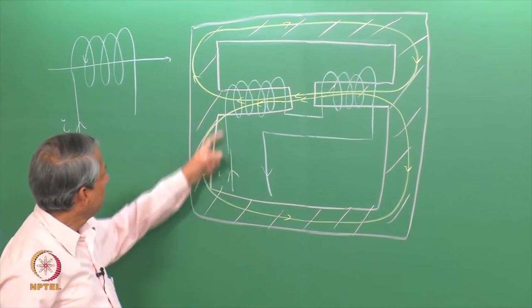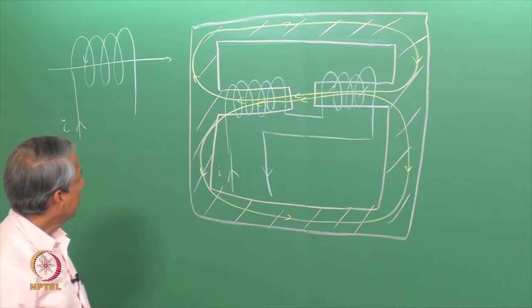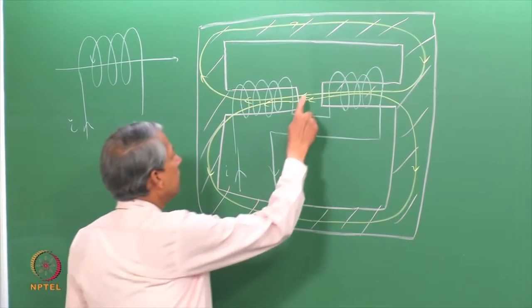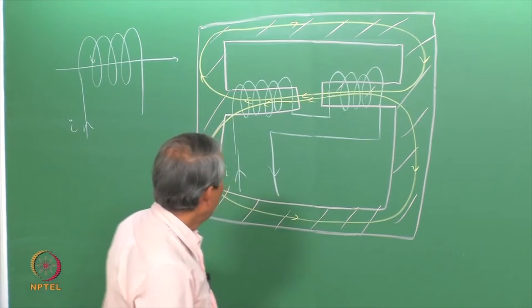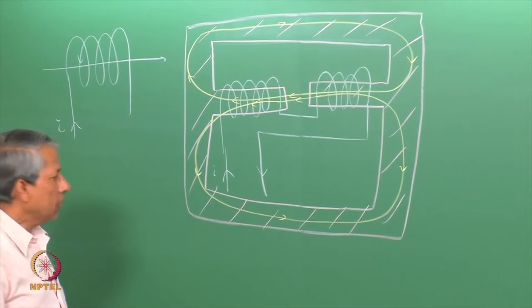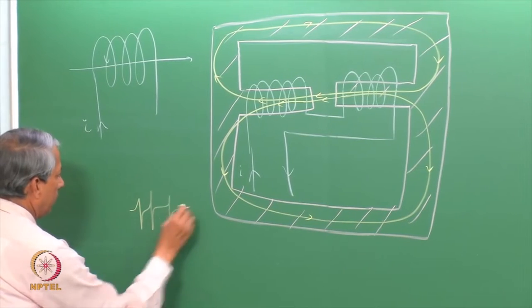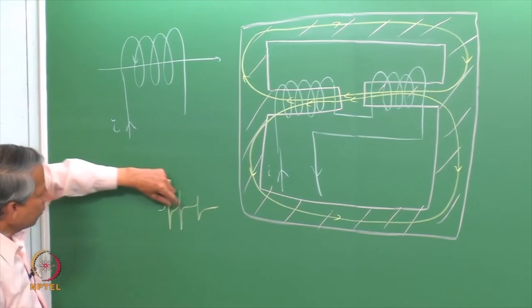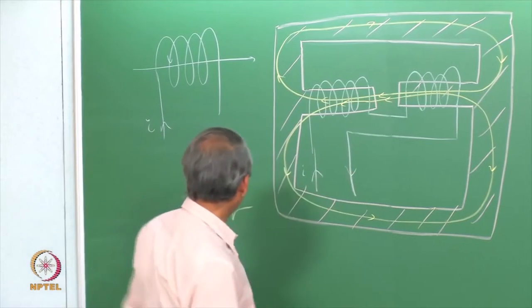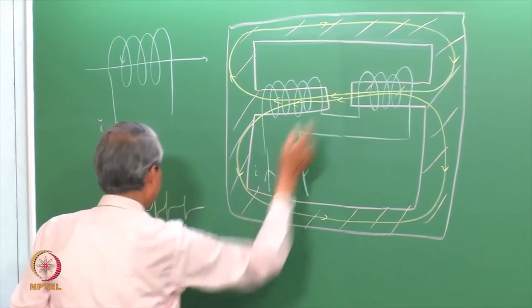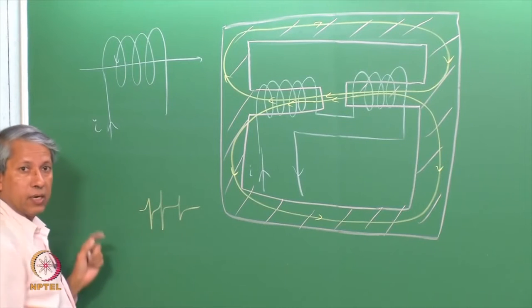As current can be varied, then the magnetic field also varies. What is required is that the magnetic field that is seen by the sample has to be very homogeneous. Because many EPR spectra come with very narrow, very closely spaced lines. If the field is not homogeneous or if the inhomogeneity is more than this width or even the separation, then these lines cannot be resolved.